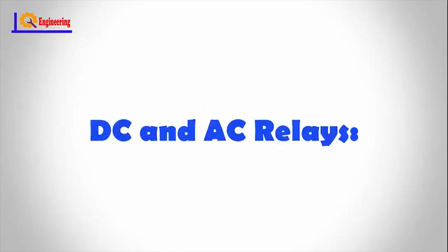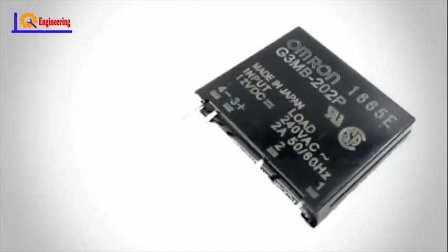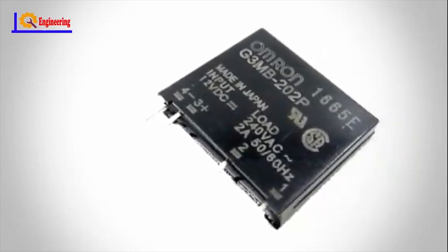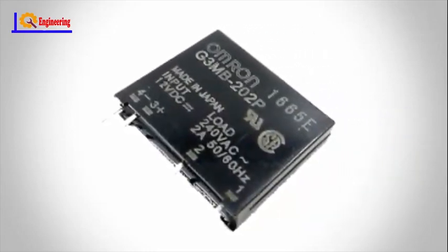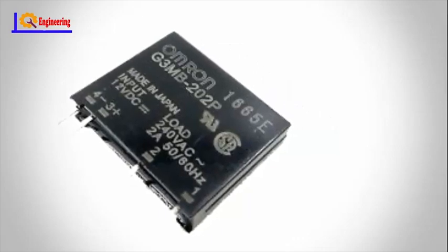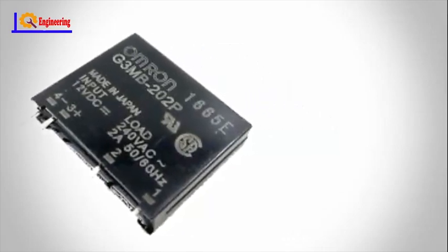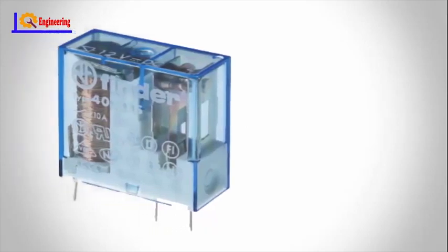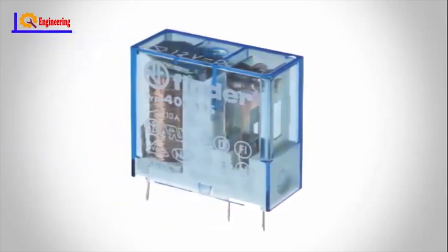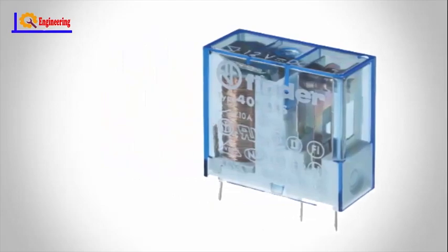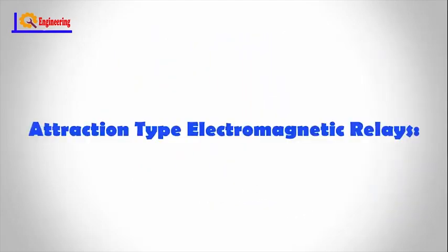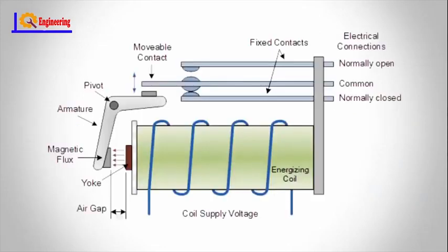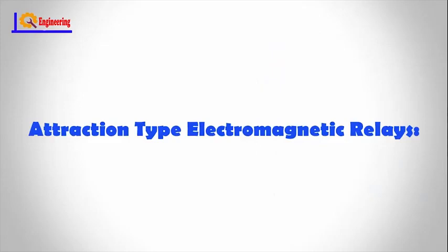DC and AC relays. Both AC and DC relays work on the same principle of electromagnetic induction, but the construction is somewhat different and also depends on the application for which these relays are selected. DC relays are employed with a free-wheeling diode to de-energize the coil, and the AC relays use laminated cores to prevent eddy current losses.